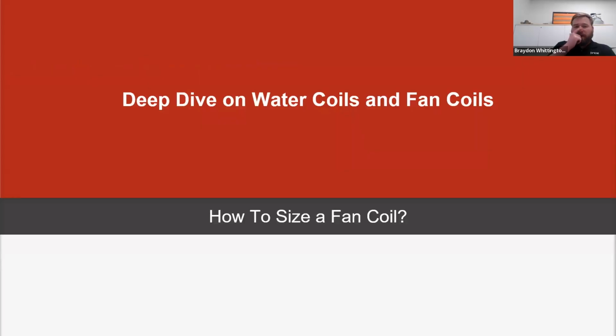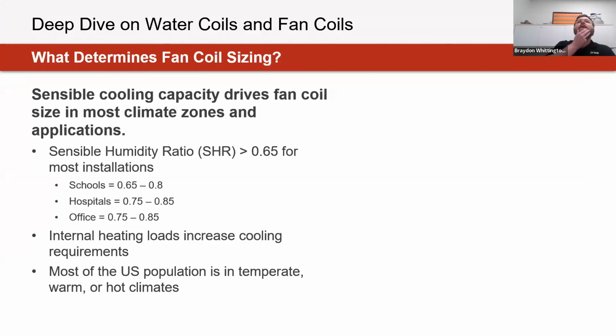The last portion here is going through an example of how to size a fan coil. Now that we look at the design side of things, what does a typical layout look like when laying out a fan coil for a system? We'll even look at a case study for this. Commonly, it's dependent on climate zone, but it's going to tie down to sizing them based off of your sensible capacity for a system. I would say most of the US population is in warm or hotter climates, but that's not to say it can't be used in colder climates as well. But more often than not, this is going to be sized based off of a sensible cooling load for a system.